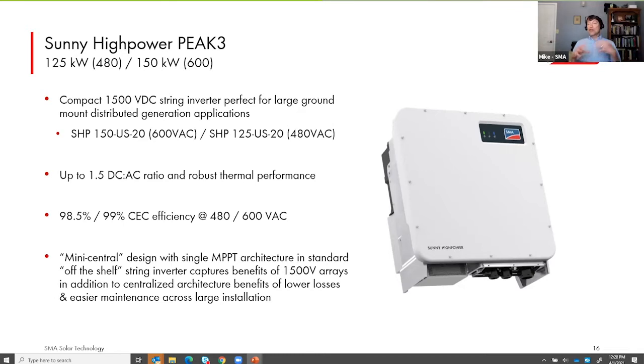So if you built a 2 megawatt system, rather than having a single 2 megawatt central inverter, that if it fails or has an issue, as long as it's offline, there is no power production from the system. If you break that up into multiple of these Peak 3s, if there's an issue with one inverter, overnight, a crew can come out, you might have a spare on site. They can swap out the inverter. You have all of that flexibility for that smaller power conversion system, high efficiency.